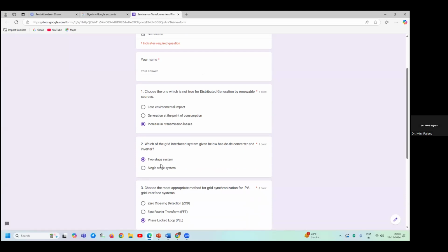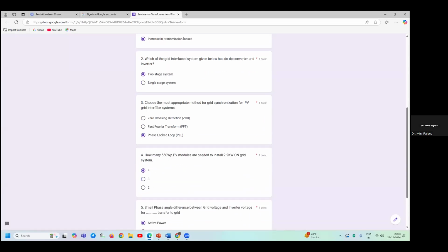Now, which of the grid interface systems given below has a DC to DC converter and inverter? The answer is the 2-stage system. Next was: choose the most appropriate method for grid synchronization. That was phase lock loop. Other methods, zero crossing detection and fast Fourier transform, have drawbacks. If harmonics are there, there are issues.